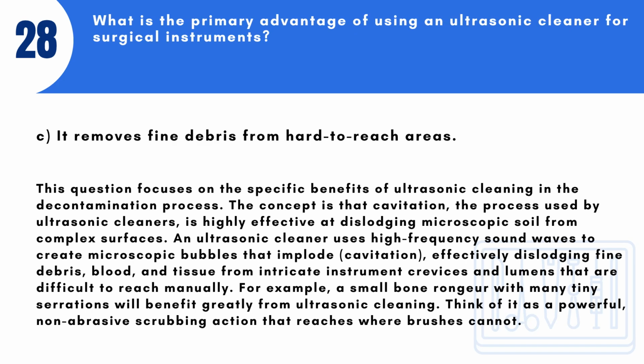Answer: C. It removes fine debris from hard-to-reach areas. This question focuses on the specific benefits of ultrasonic cleaning in the decontamination process. The concept is that cavitation, the process used by ultrasonic cleaners, is highly effective at dislodging microscopic soil from complex surfaces. An ultrasonic cleaner uses high-frequency sound waves to create microscopic bubbles that implode, cavitation, effectively dislodging fine debris, blood, and tissue from intricate instrument crevices and lumens that are difficult to reach manually.